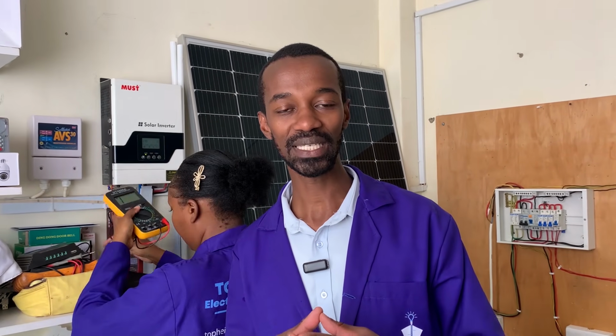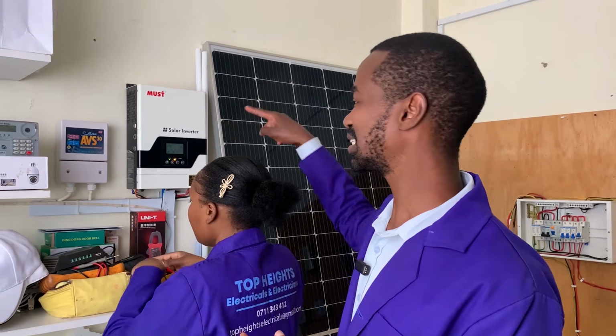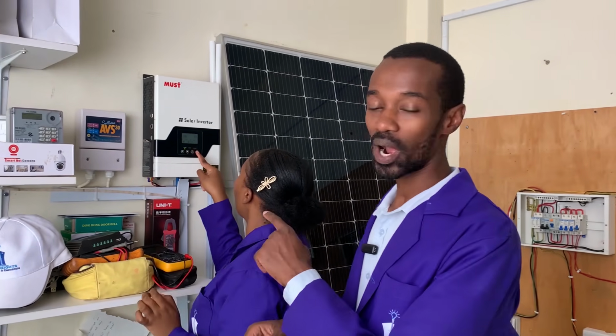The first step when disconnecting the inverter is to switch off the AC supply, followed by the solar panels. These carry a lot of voltage that can damage an inverter in the event that it is not actually powered by the battery itself. After all those high power charging systems are disconnected, we then go ahead and disconnect the battery. So top bosses, let's go ahead and do that.